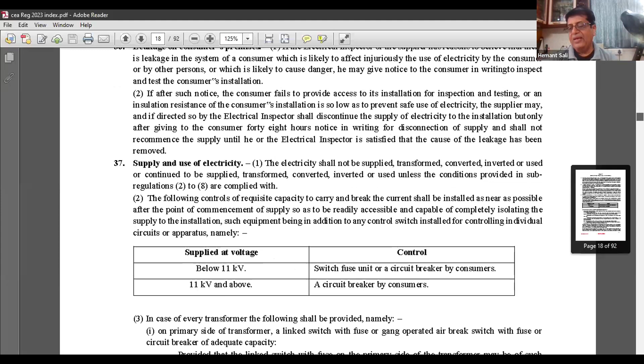One thing, if we consider from the perspective of supply companies, if we don't have a proper tripping device at the source of supply placed by the consumer, the fault may pass on to the substation and that may affect more area. So I think this could be the requirement given from the supply companies, that there should be a breaker at the point of supply so that tripping in the substation may not occur. So this could be the reason. But again, suppose for a 100 kVA transformer, if you need to install a VCB, financially it is a very, very big burden to the consumers, and such cost goes above the cost of the transformer. So this is again the point. This again I have sent to CEA also for reconsideration. Let us see what happens.